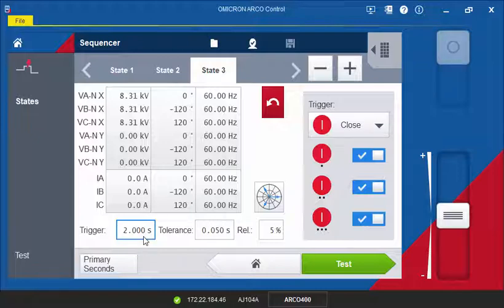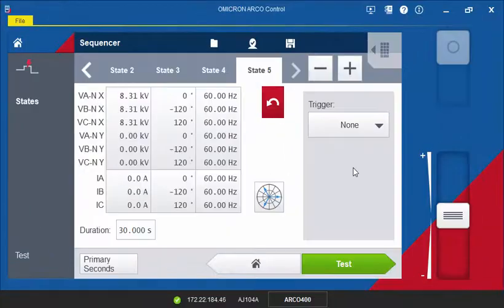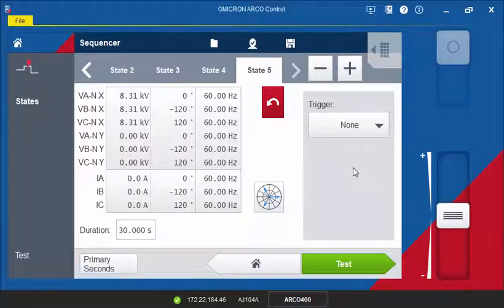That's it! In the same way, we can now configure the rest of the states. The final state is the lockout state. We will output zero current for 30 seconds. The duration of the lockout state has to be set long enough to make sure that the controller is in the lockout state and doesn't reclose again.